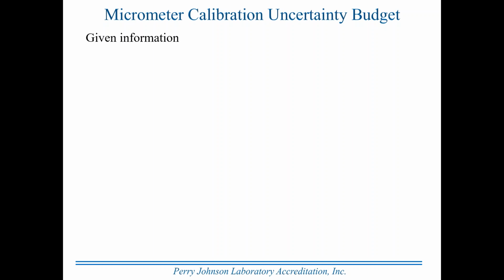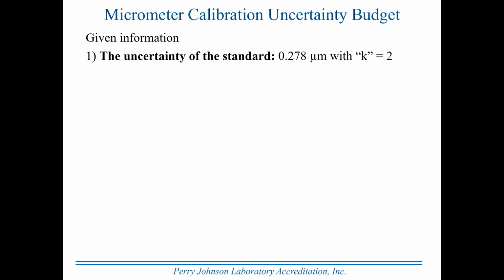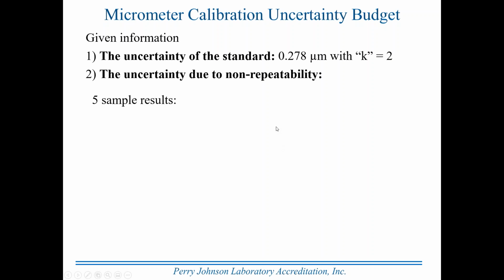Okay, let's look at some given information for this calibration. The uncertainty of the standard is 0.278 micrometers with k equals 2. The uncertainty due to non-repeatability: we're going to take 5 sample readings and take the average. Remember, two things that we said: the average of multiple readings is the best indicator of the true value, and the reason that we take 5 readings and all of them are slightly different is because of random variation, primarily in the measurement device. It's the measure of the limitations of the measurement device for sure.